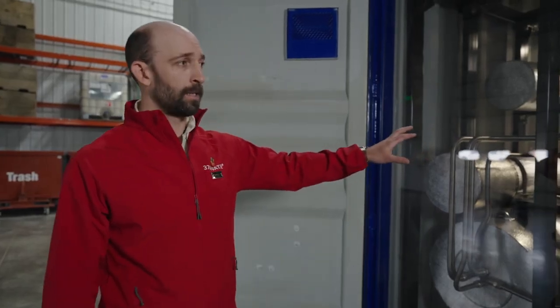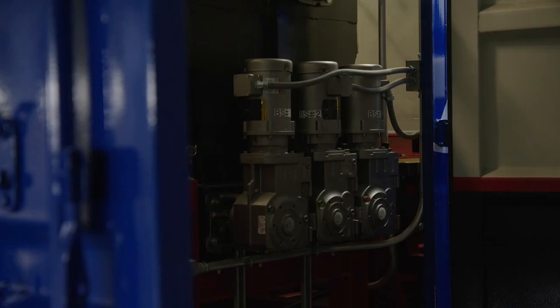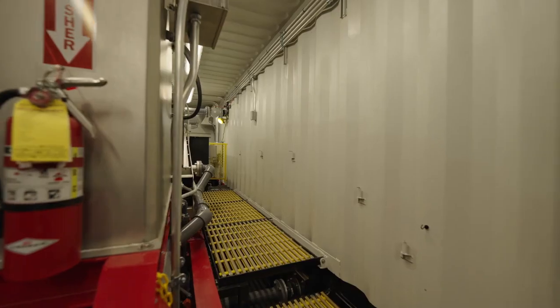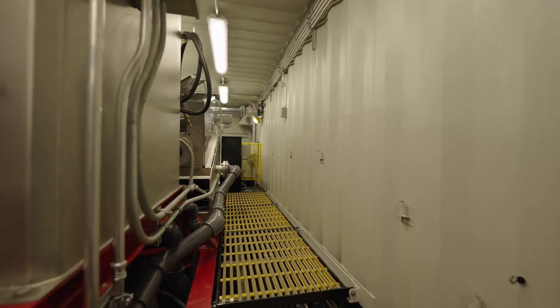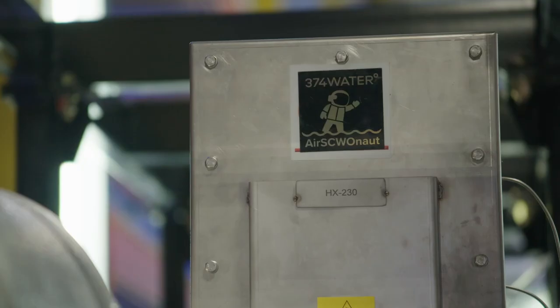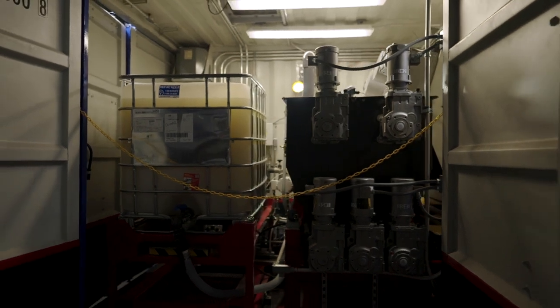This is the AirSCWO system operating. Right now we are processing the biosolids that we've seen first in the dumpster and then going through the dewatering system. This is bringing those same biosolids up to 3,400 psi — that's about 220 times atmospheric pressure — and adding a significant amount of heat, over 374 degrees Celsius, 705 degrees Fahrenheit, to the reactor to create a very complete and very fast oxidation process. What exits this system is clean water, a mineral brine, and vent gas.